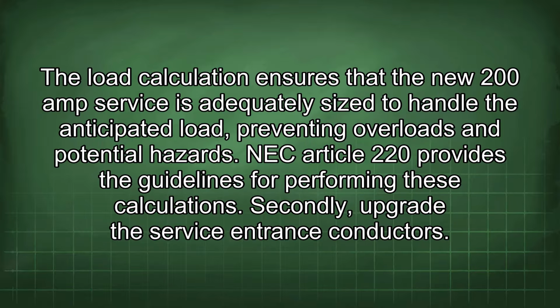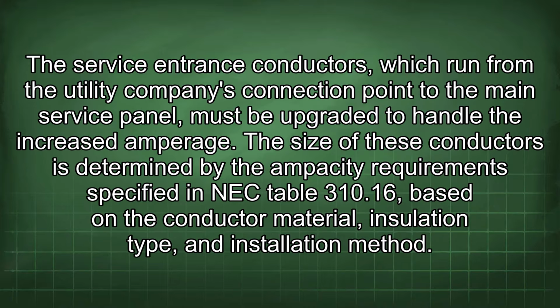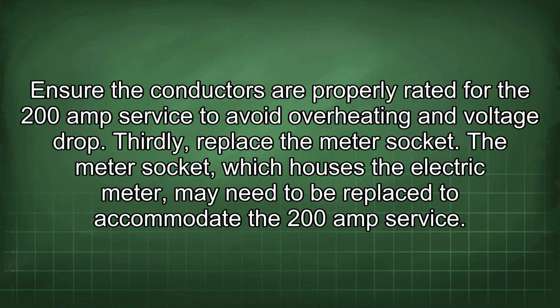Secondly, upgrade the service entrance conductors. The service entrance conductors, which run from the utility company's connection point to the main service panel, must be upgraded to handle the increased amperage. The size of these conductors is determined by the ampacity requirements specified in NEC Table 310.16 based on the conductor material, insulation type, and installation method. Ensure the conductors are properly rated for the 200 amp service to avoid overheating and voltage drop.